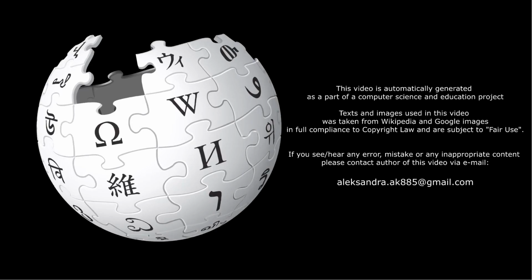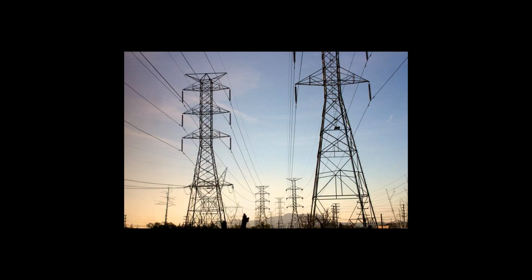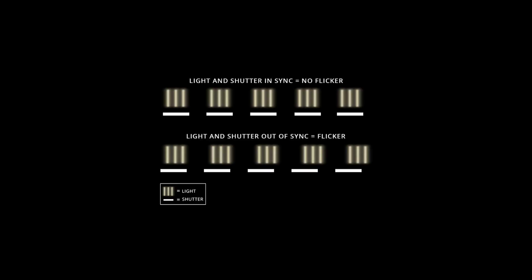In the standard IEC 61000-3, the observation intervals and the limiting values for PST and PLT are specified. Operating condition of the EUT. The IEC flicker standard states that the EUT, the equipment under test, has to be operated during the test in a way which is the worst-case state with respect to flicker.